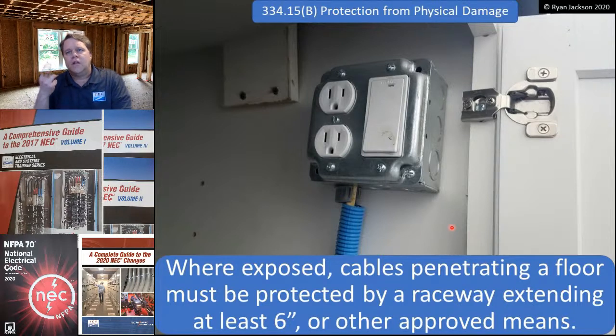Okay, so this is obviously an exposed NM cable. This is underneath a cabinet, and this is for a disposal. We've got our switched receptacle. So it penetrates through the floor from the basement, and we have to have some sort of a raceway that extends up at least 6 inches. In this application, we decided to extend the raceway pretty much all the way up to the box to add that additional protection. Does it need to go all the way to the box? I don't think so. I think that's okay.